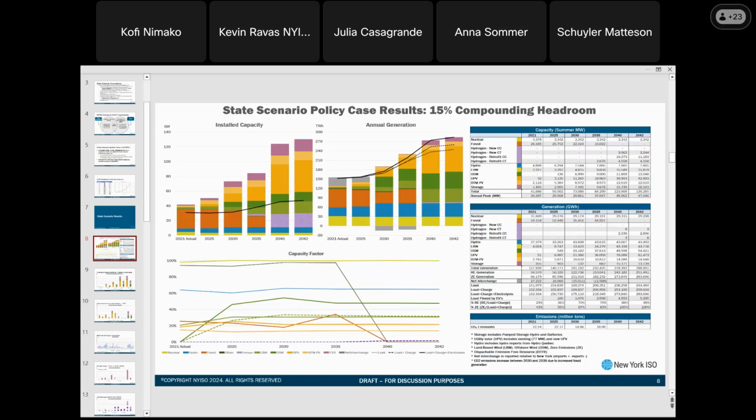And so if you have like 4 or 5 days straight with low peaks and high over generation, you can only really charge that battery once, and you might not have a time to discharge it that makes economic sense. So there's a chance that in a 36 to 48 hour over generation period, you only charge for the first 4 hours. And then a lot of those other hours are either making hydrogen or just being curtailed, or exported.